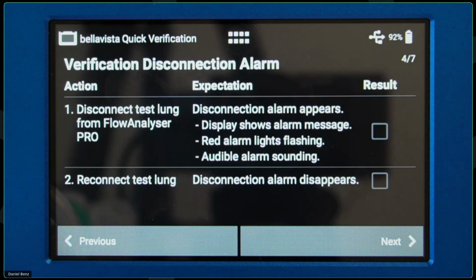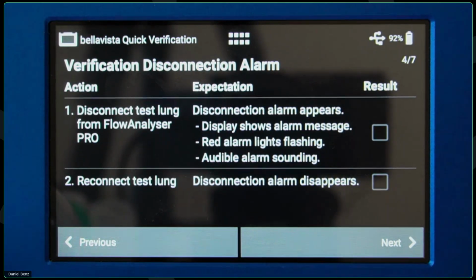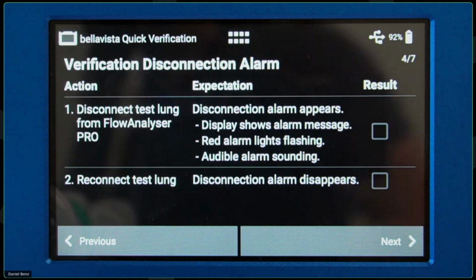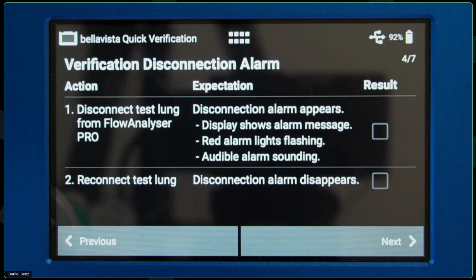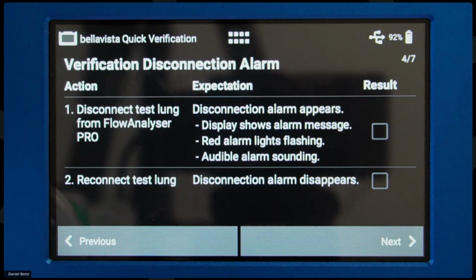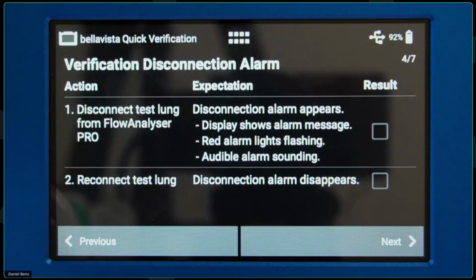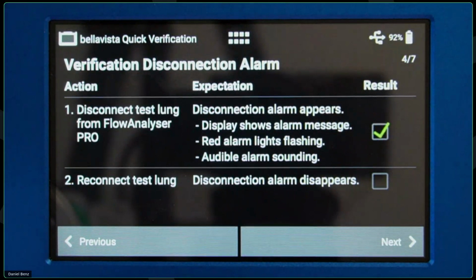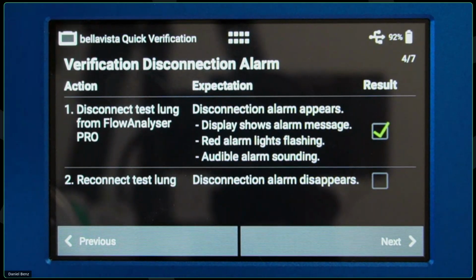In this case, I'm asked to trigger a disconnection on my ventilator. I'm gonna do that quickly here, and then I should hear an alarm of my vent. So you can probably hear it in the background, it alarms. So I confirm, yes, that happens. Then it asks me to reconnect and the alarm should disappear. Yep, that happened. So I confirm here.